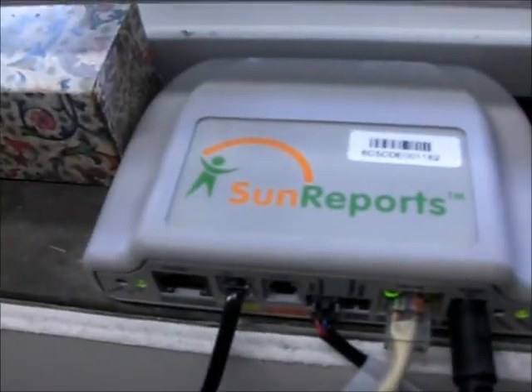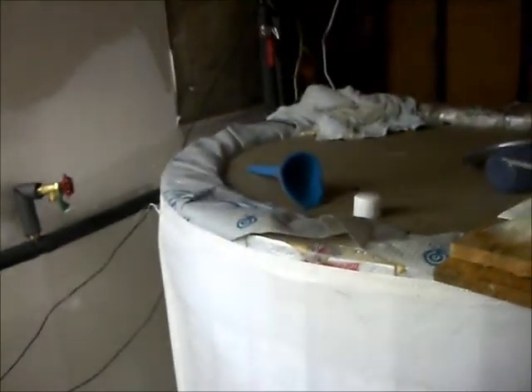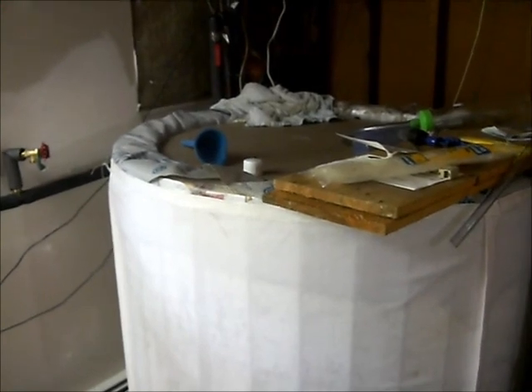As far as tank size goes, 210 gallons is kind of the bare minimum here in Vancouver, BC — we don't get that much sunshine. When you have three, four, or five days of steady rain and no sun, the tank temperature tends to drop, and every shower drops it five to ten degrees Fahrenheit. Get as big a tank as you can afford. In Calgary you can get away with maybe an 80 or 100 gallon tank for a 130-tube collector, but here where we don't get much sun, go as large as you can — or even two 210-gallon soft tanks run one after the other.